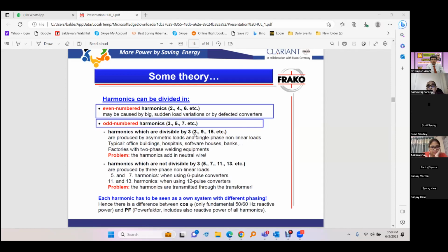They are normally found in single phase loads, where the concentration of single phase loads is higher. Like in IT installations, hotels, hospitals, commercial buildings, we will find this zero sequence, third harmonic mainly. What happens is these harmonics, along with the unbalance in the system, flow through the neutral, and the neutral gets overloaded. So what we have to do is strengthen the neutral. In IT installations, we find they use a 5-core cable. They use 2 cores for the neutral and 3 cores for the phases, because the neutral current could be more than twice the phase current.